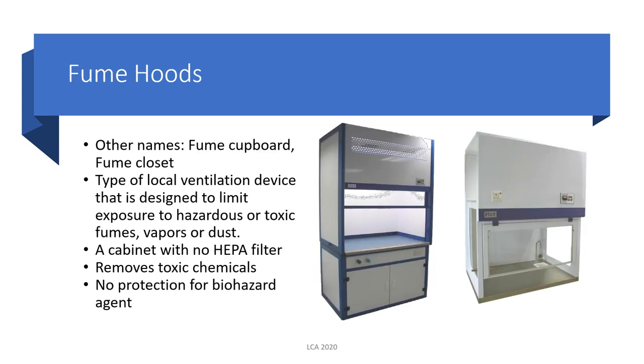Our first type of cabinet is the fume hood, also known as the fume cupboard or fume closet. This is a type of local ventilation device designed to limit exposure to hazardous or toxic fumes, vapors, or dust produced by the chemicals we handle inside the laboratory. This cabinet does not contain any HEPA filter, so there is no protection for biohazardous agents. Its only function is to remove toxic chemicals.